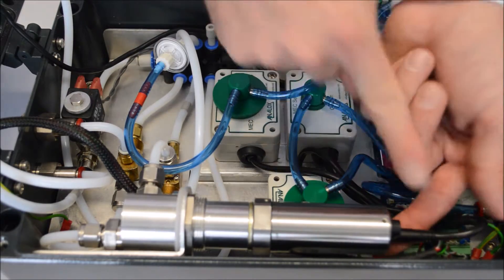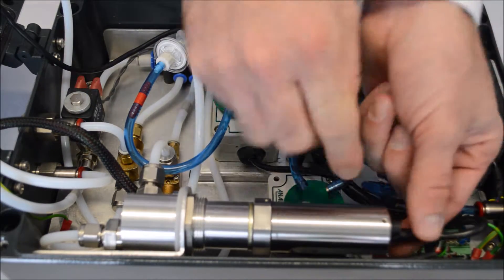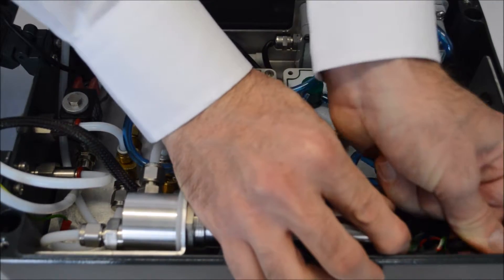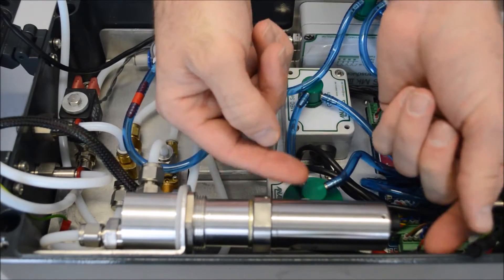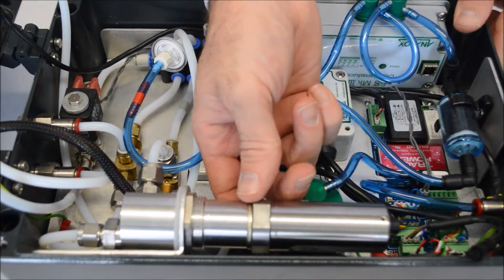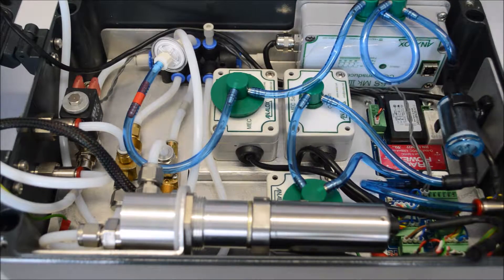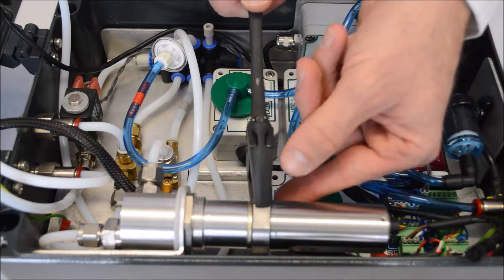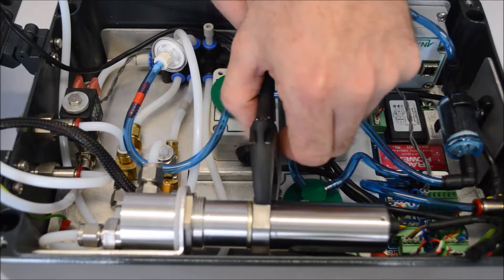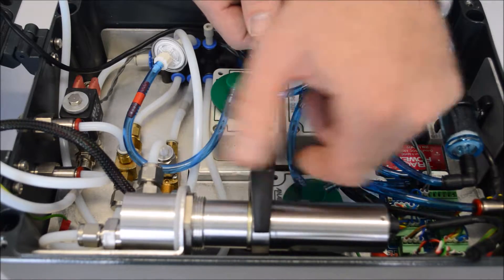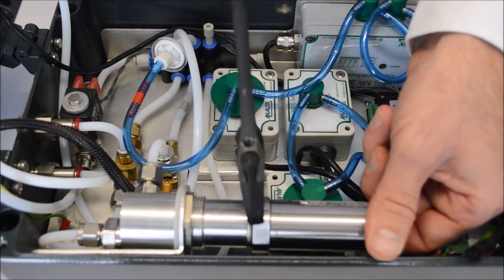So initially we need to disconnect the cable off the end of the unit by pulling directly in that direction, and then we need to remove the dew point sensor using a 30mm spanner or an adjustable spanner. Connect on and gently slacken it off.